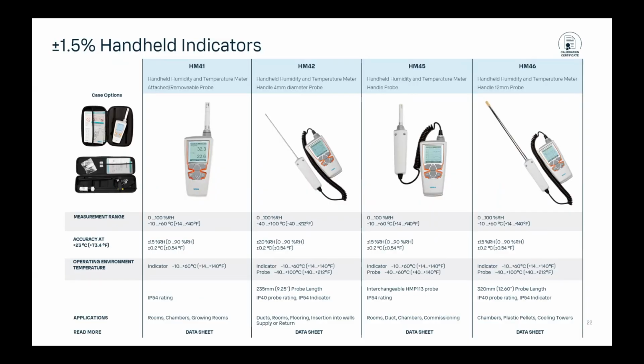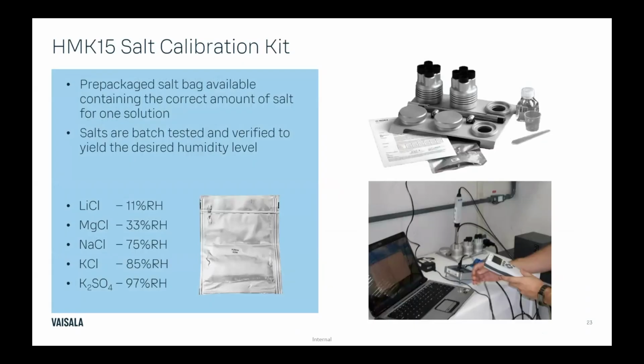And then just to highlight this, if you ever are interested in doing your own calibrations, we have an HMK 15 salt calibration kit. So how this is used is we offer 5 different calibration salts that create reference environments, anywhere from 11% to 97% humidity. This salt is mixed in a chamber with deionized water, and it produces a known reference value. So typically we see 2-point calibrations, so say 11% and 75% relative humidity. You can connect to a PC or that Indigo 80 handheld, calculate your reference environment, and then make the adjustment of the probe you're looking to adjust.